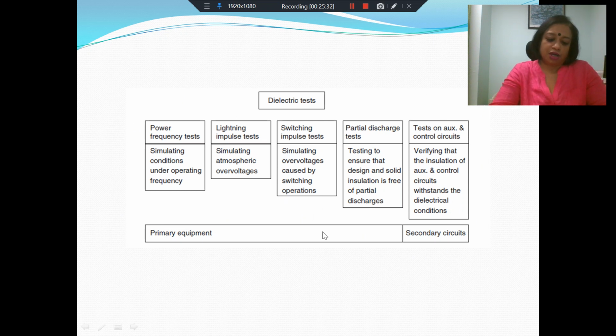So all in all, gas-insulated substations are a considerable improvement over air-insulated substations. They come with a lot of advantages, but they're much more expensive, much more difficult to build. But at the same time, once it is in place, we have to bother less about it. They do not need so much periodic maintenance. They have better life, but there are issues connected with them as well. A lot of research is geared towards condition monitoring of GIS through PD monitoring.